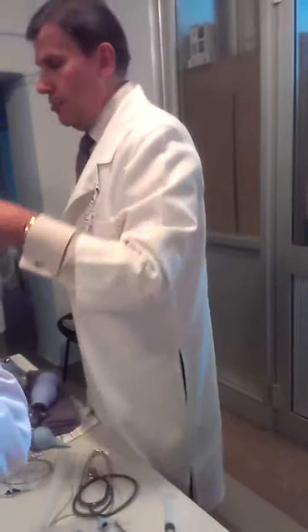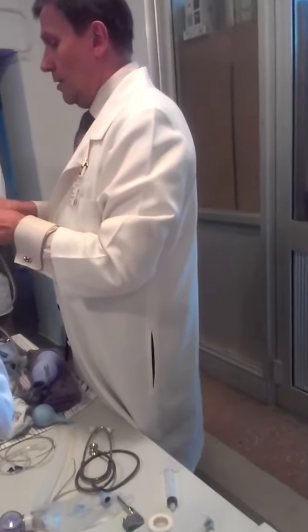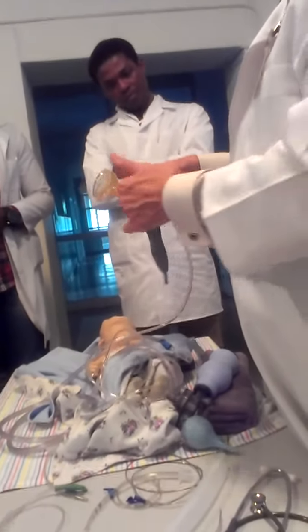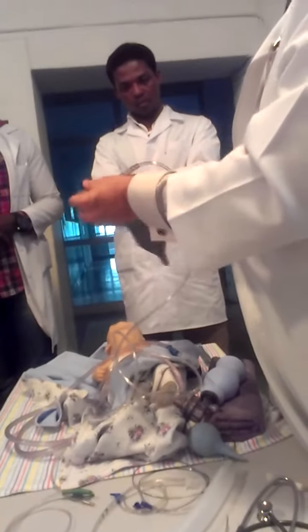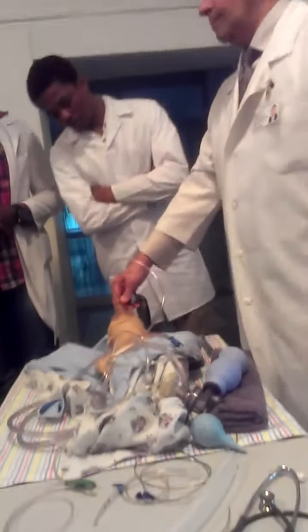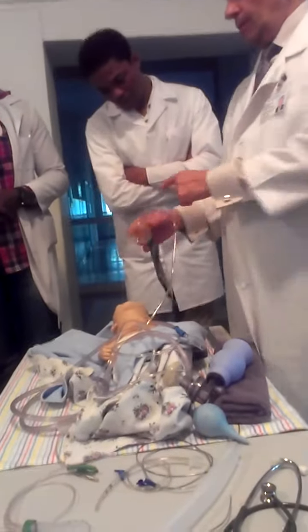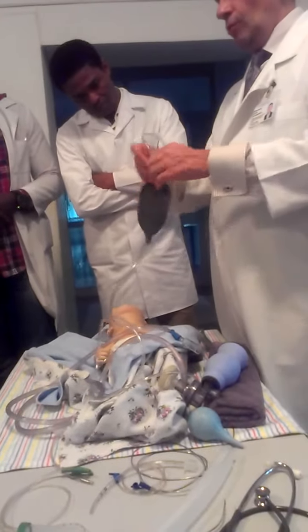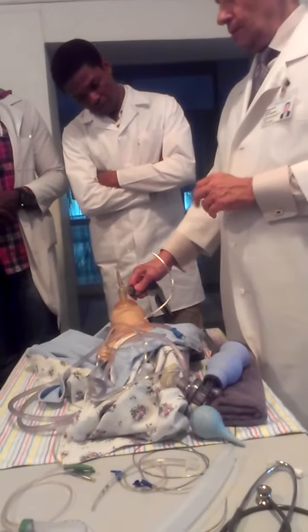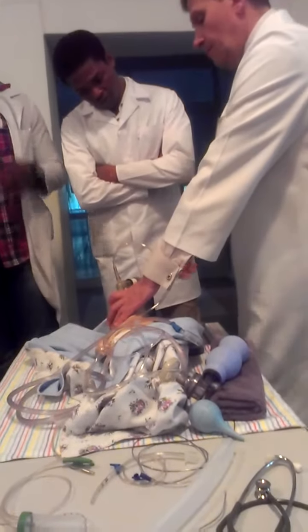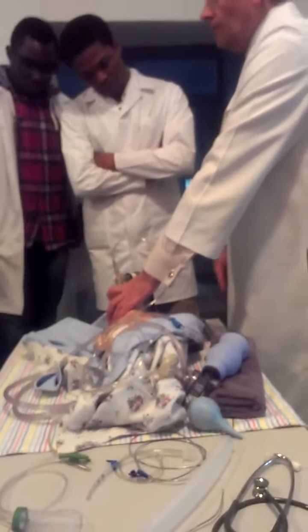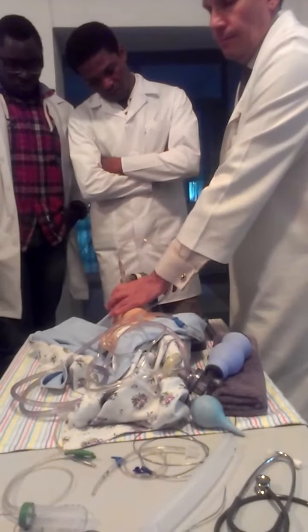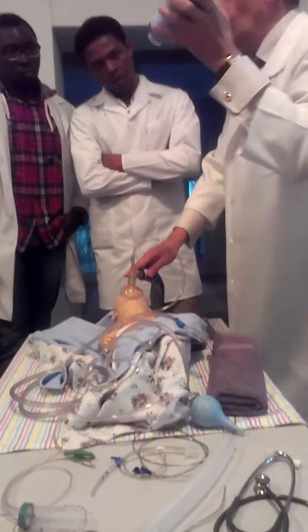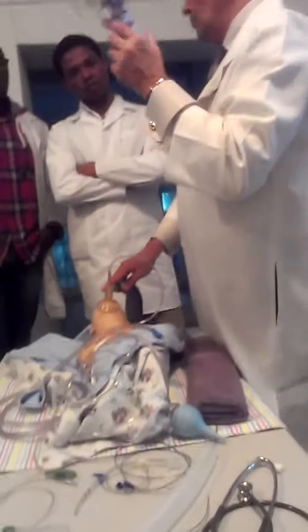This is regular oxygen tube. You're going to connect it here. And you may put here not oxygen but air. If you have a source of compressed air, you may put here air. Then you have a flow. Okay, but to fill this bag, you must create a seal. Okay, because otherwise it's coming here and escaping here. No inflation. To inflate, you must create a seal. And if this bag will start inflating, it will tell you that you created a good seal. It's not for this bag. It's always inflated, and you don't know if you created a good seal.